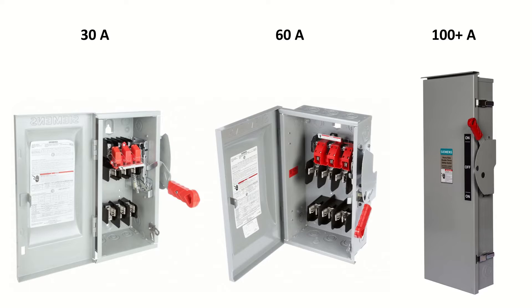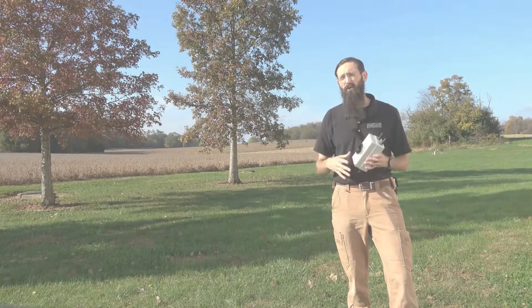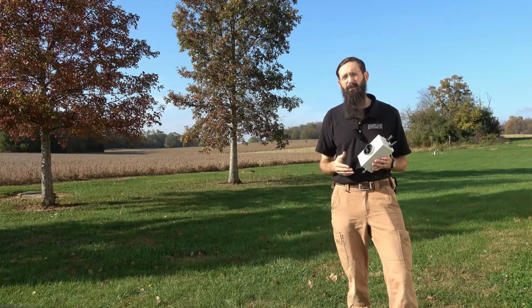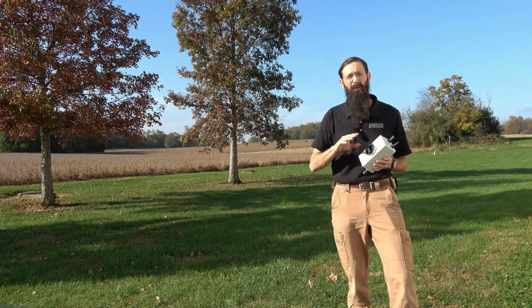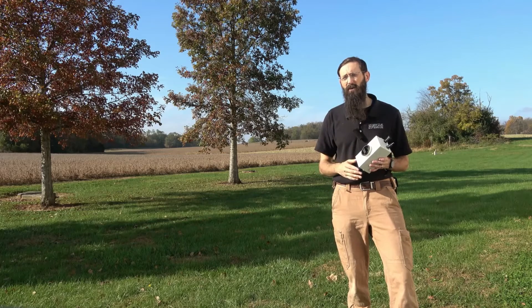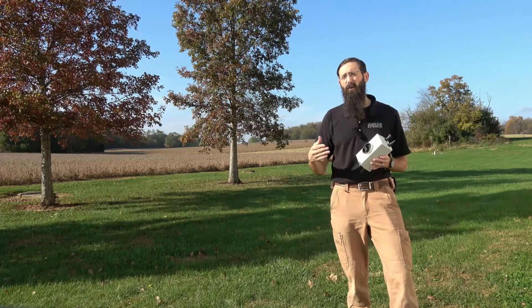The sizing is a function of your voltage, circuit load, amperage or breaker size, as well as the wiring or cable size. If you include a standalone DC disconnect in your circuit, then you'll have to size it in the same manner as the junction box or the combiner box. In many cases, the appropriate model for your circuit will be rated for 600 volts DC. You'll likewise have the choice of a fusible or non-fusible switch.